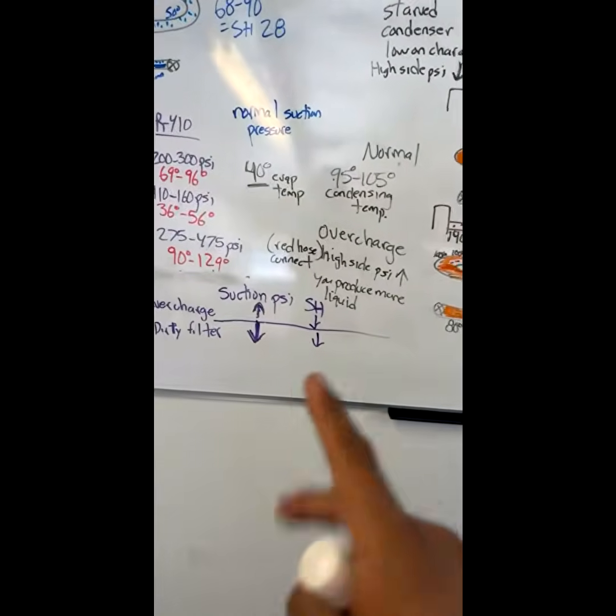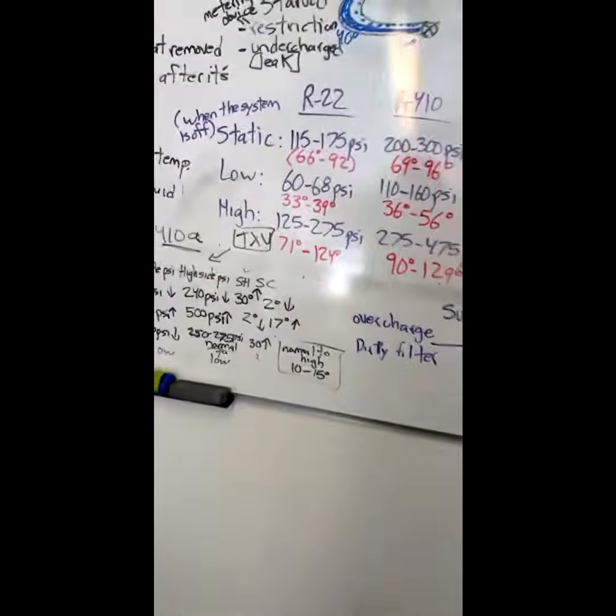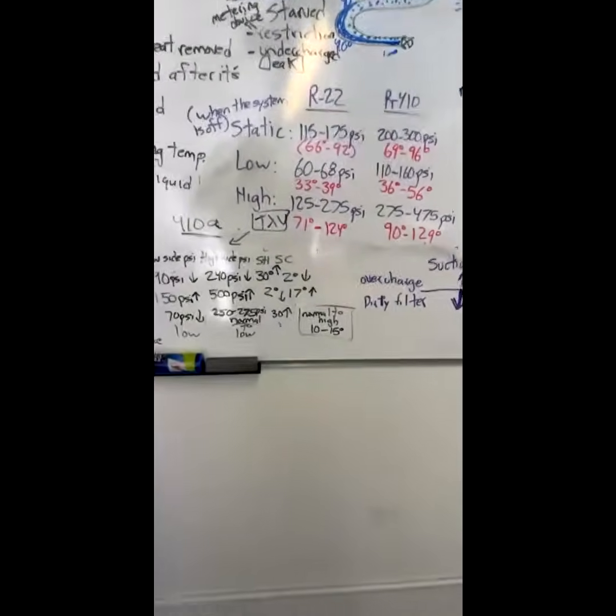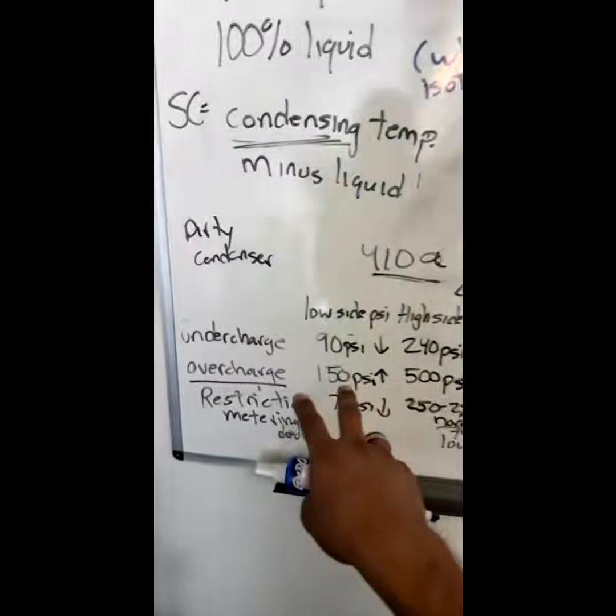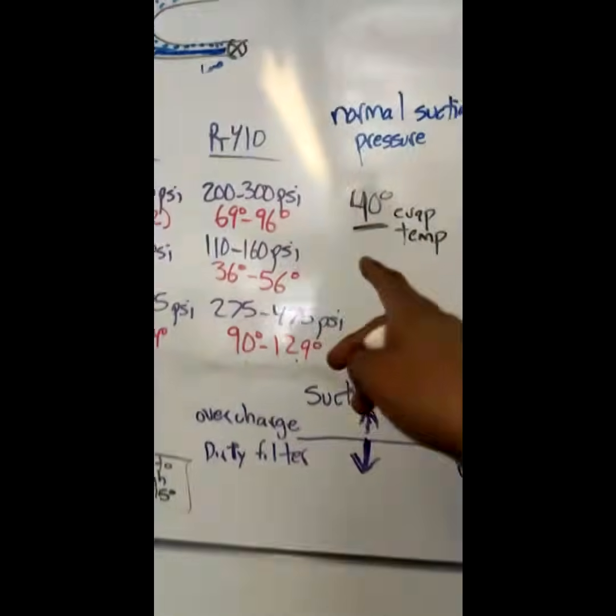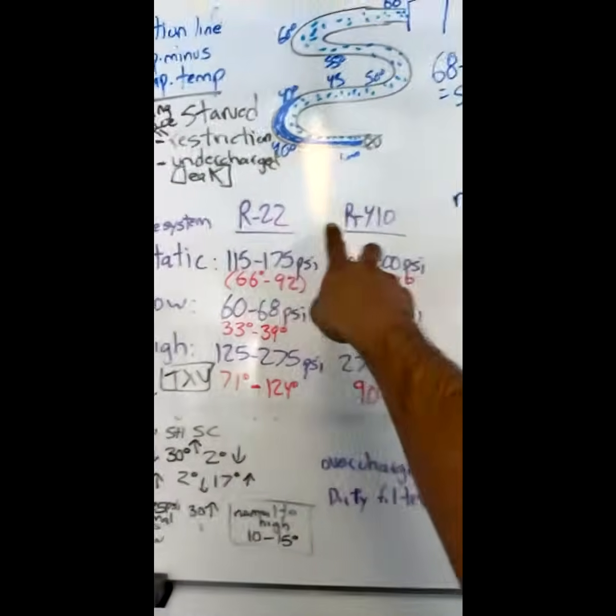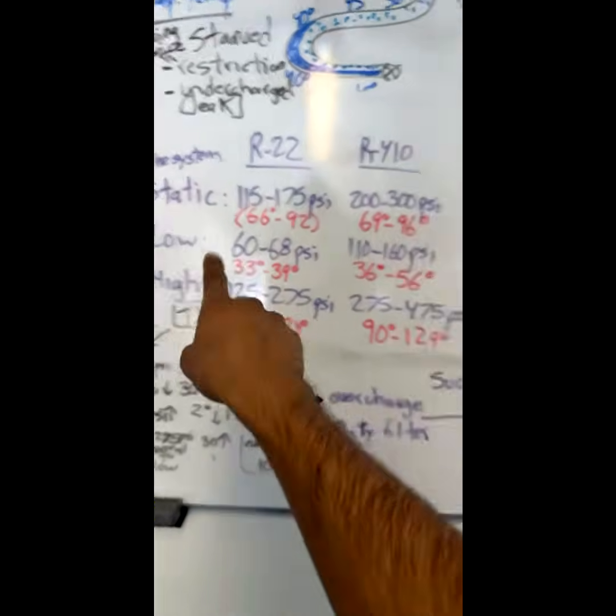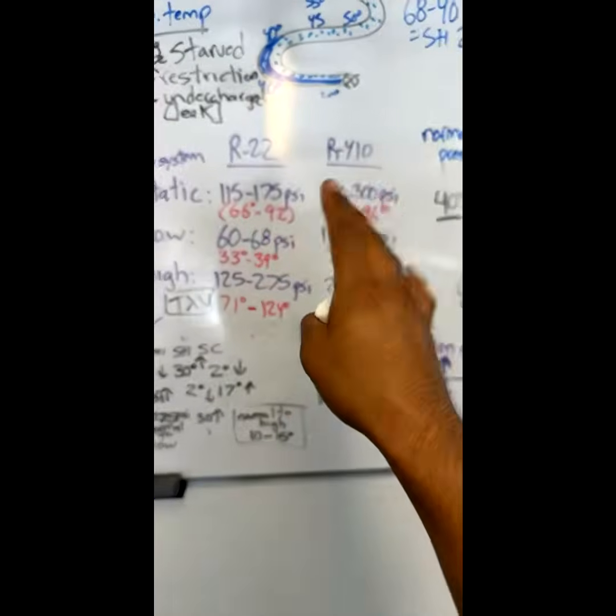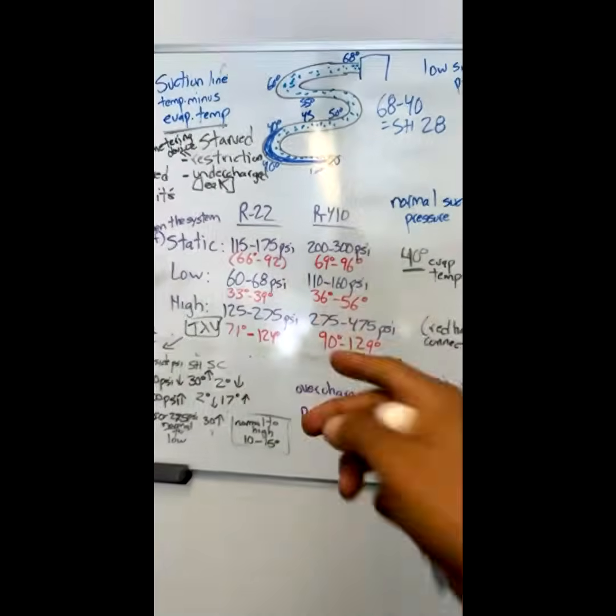So, that's the idea with superheat and subcool. We're just going over superheat and subcool. I kind of went over some numbers. If you guys are in a school, and let me just emphasize this: if you are not learning about superheat and subcool, you've gotta tell them what's up. It's no longer just pressures, right? And there is a range for R22 and 410A when it's static, low and high. There are ranges of pressures that you should be looking at. Of course, that can change. It's just a rule of thumb.